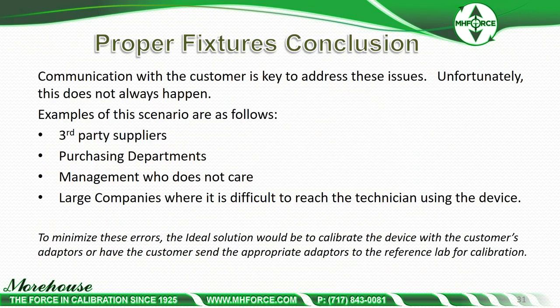That concludes our discussion on fixturing. Communication with the customer is key to address these issues, but unfortunately it does not always happen. Examples: third-party suppliers where you can't talk to the end user, purchasing departments that won't connect you to the end user, management that just wants a sticker, and large companies where it's difficult to reach the technician using the device. The ideal solution is to calibrate the device with the customer's adapters or have them send the appropriate adapters to the reference lab for calibration.